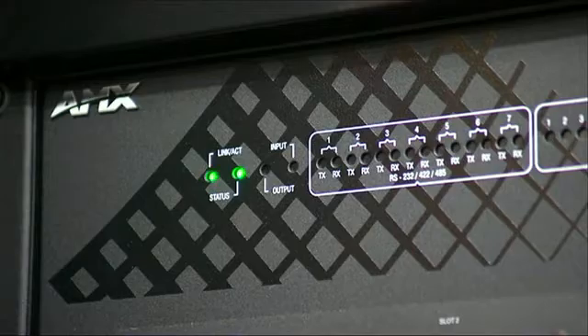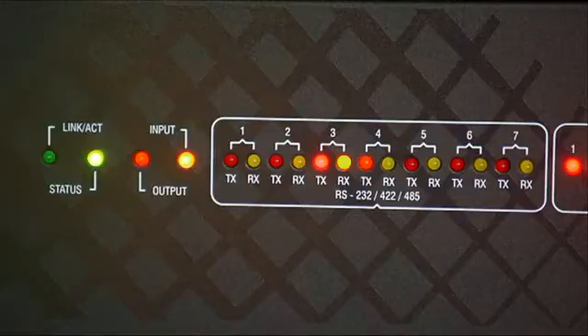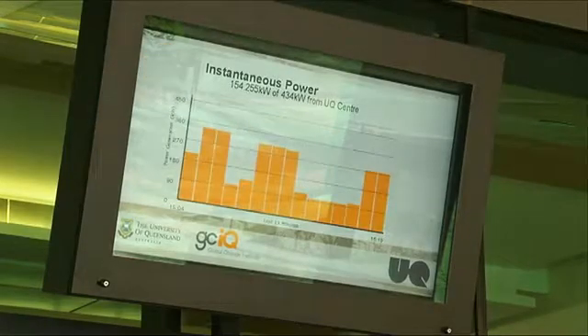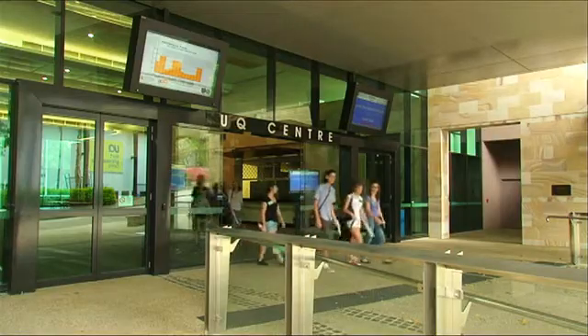AMX NetLinx controllers interrogate Red Lion PLCs via Modbus over the IP network in order to read all data from the seven sites that make up the solar array. We stored that data in a data structure, and as the pages change, the AMX sends out HTML formatted charts to the players that are then displayed by those AMX Inspired Signage players.